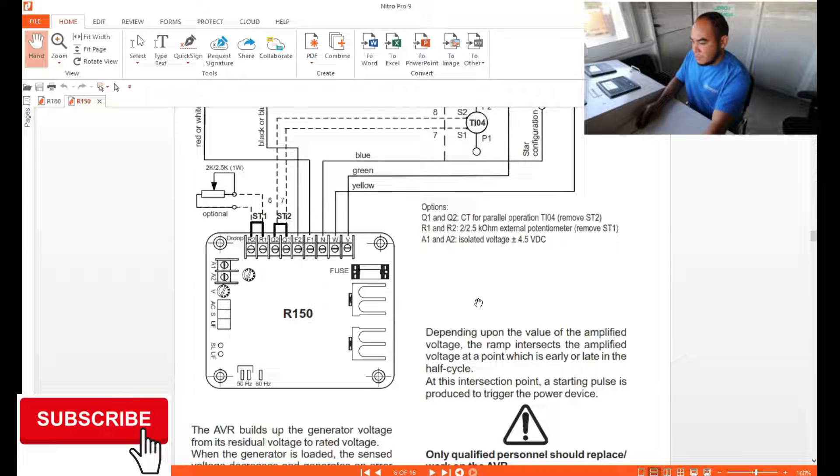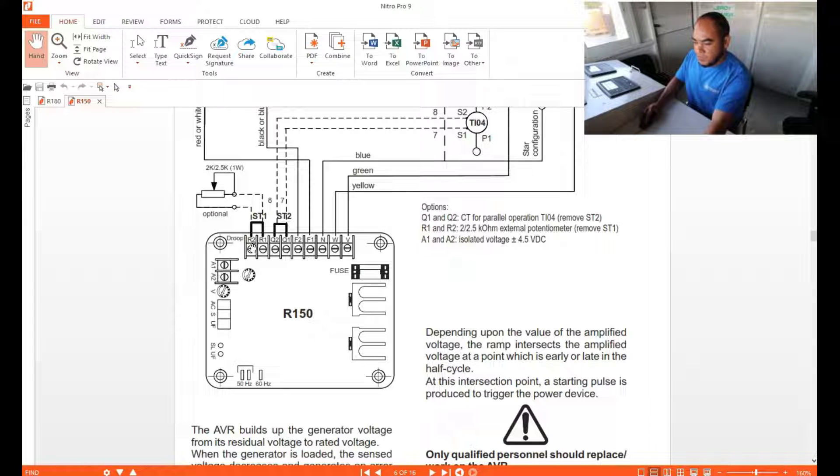Q1 and Q2 are for paralleling operations. Remove the link at ST2, then connect your wiring from your droop CT. For R1 and R2, the external potentiometer — remove the link ST1 and install your wiring. Make sure that your potentiometer connections are correct, because if wrong, instead of adding voltage it will subtract. So just be careful about that.